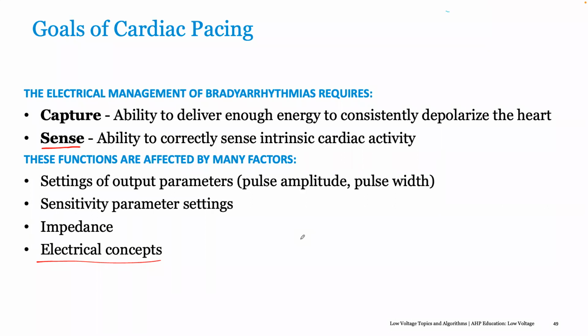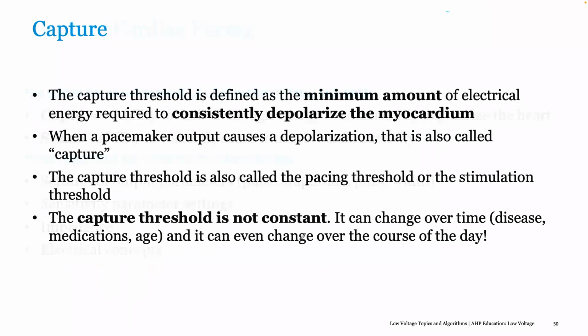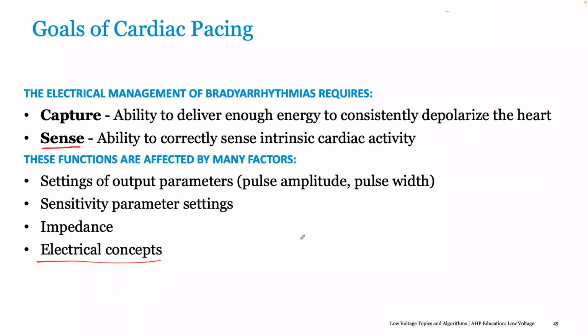The other thing, and you can confirm as you're the expert with Abbott, but the one thing I do like about your devices is with your Cap Confirm, instead of having the auto threshold at double the output, yours works almost on a beat to beat. Is that correct? Yeah, correct. So you place 0.25 above threshold, but if there's no evoked potential after the spike, then you hit with a 5-volt output as a backup pulse. Correct. Yes. So that's how our system works for auto capture.